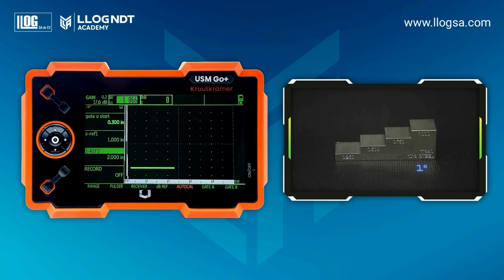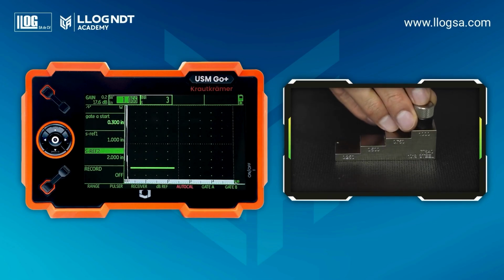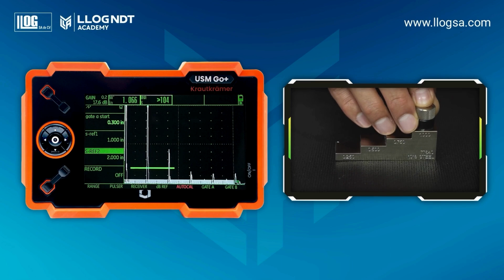Now place the probe on the 1-inch thickness of the block. Adjust the gain until the first echo reaches approximately 80% of full screen height. This is only for reference. In the record function, press the right navigation key once to activate auto-calibration. To save the first reference, press the right key again. For the second reference, move the gate to the second echo. And press the right key in the record function.